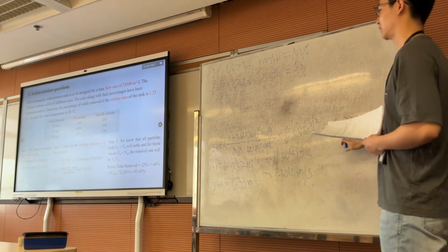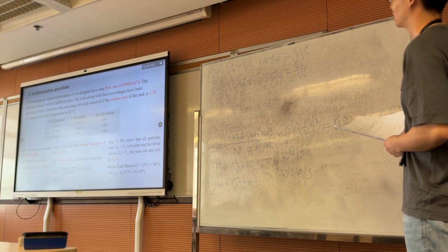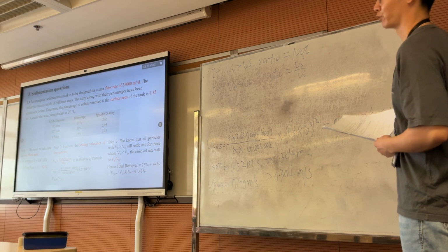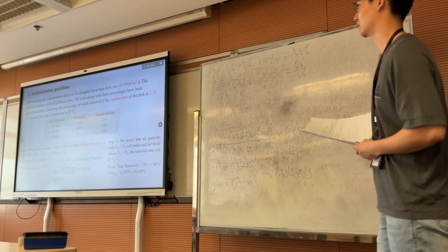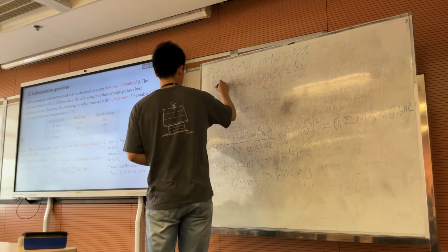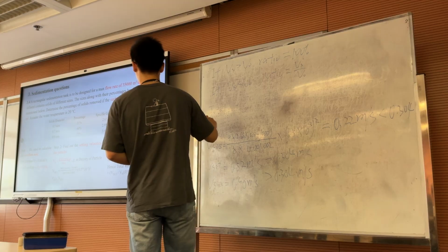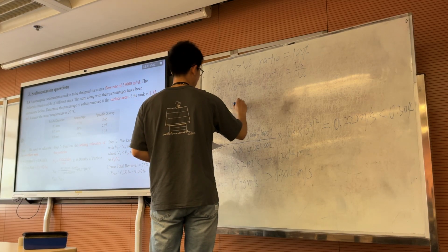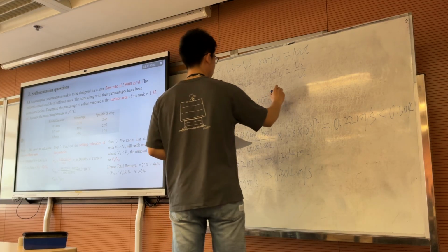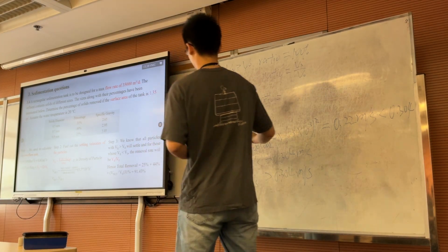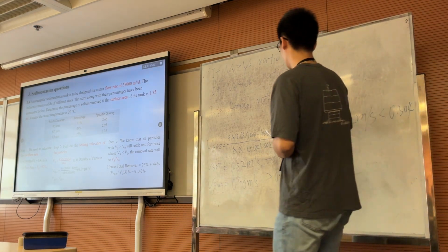We can do the comparison here. For this particle, the settling velocity is smaller than the overflow rate, so this particle cannot be completely removed. The other two particles can be removed by this sedimentation tank.